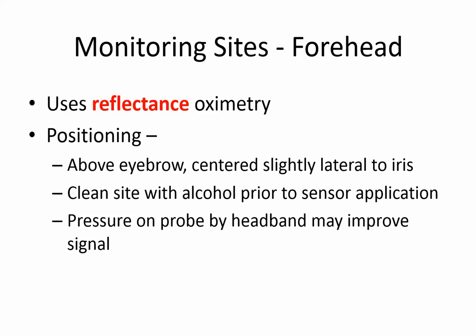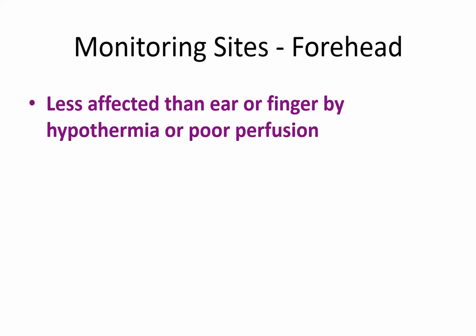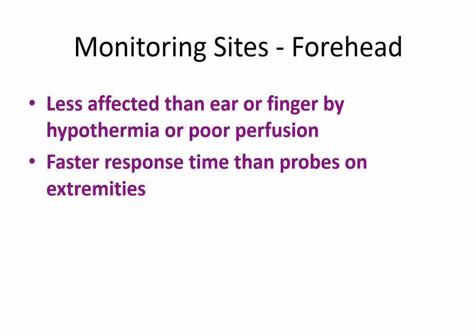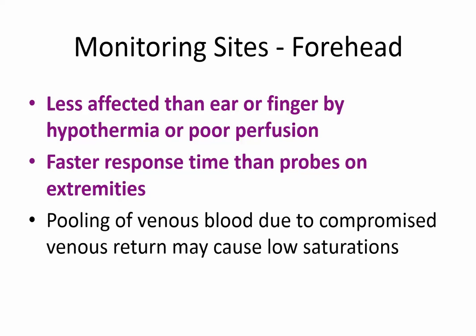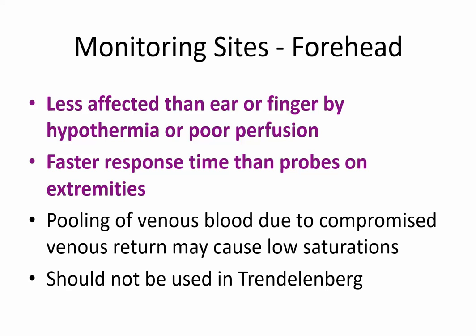The forehead is another site. It uses reflectance pulse oximetry, so remember that for the limitations and problems associated with that. The manufacturers generally recommend that it be positioned above the eyebrow, centered slightly lateral to the iris. Some people have a headband that they put on to try to apply pressure in an attempt to improve the signal. The forehead is less affected than the ear or the finger by hypothermia or poor perfusion. It's got a faster response time, but pooling of venous blood due to compromised venous return may produce low saturations. As a result of that, some people say that it should not be used in Trendelenburg.